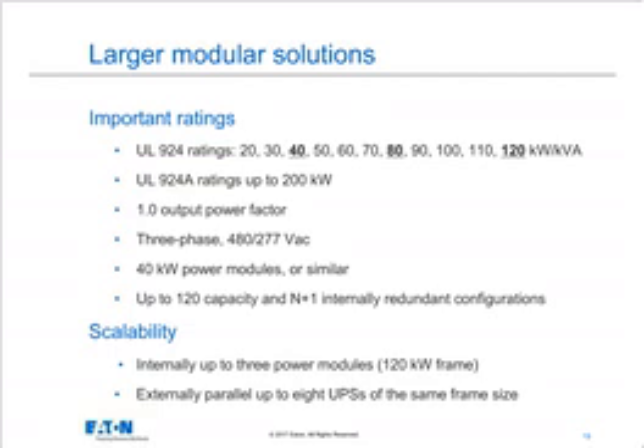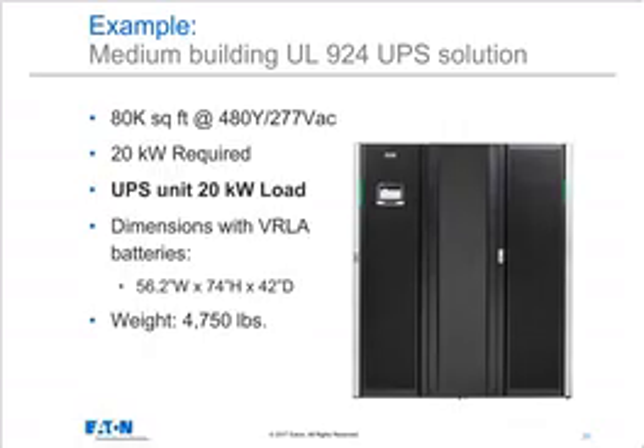In medium to large buildings, this is an example of what the UPS would look like along with basic battery. The battery could be larger depending on the actual size of the UPS. This is a 20 kilowatt load, so it's not a huge UPS. Most of that black box you see there is battery, for example, and you see the dimensions: 56 wide, 74 tall, and 42 deep, and the weight now is up over 2 tons for that UPS.